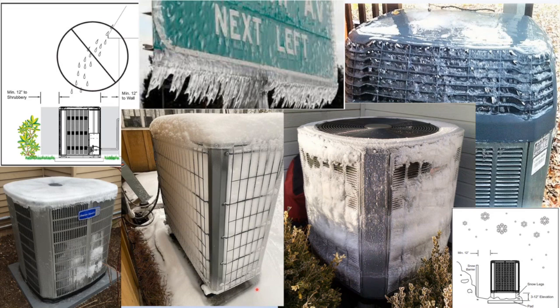Another thing that we'd be looking at is, say it's a side discharge unit and it's up on top of a commercial building's roof. Remember we said that the outdoor fan has to stop so that it gives the coil a chance to warm up and it's not fighting the cold air rushing through the coil. Well, if it's on a roof, you might need a wind baffle or something like that, because if you've got prevailing winds blowing through it, it doesn't matter that the outdoor fan shut off. With those prevailing winds going through it, it's still never going to be able to defrost. So you may need a wind baffle in that case.